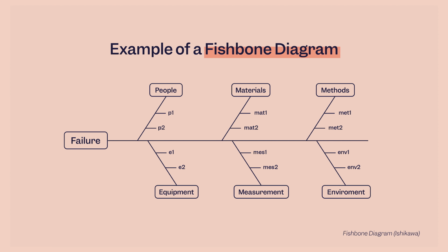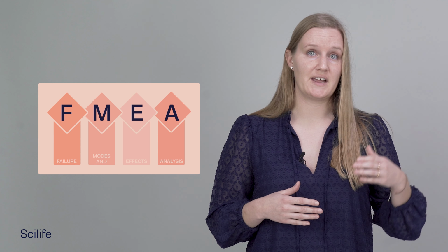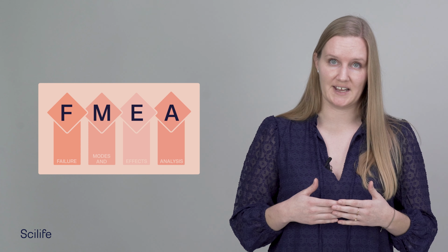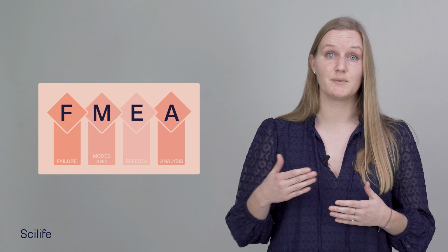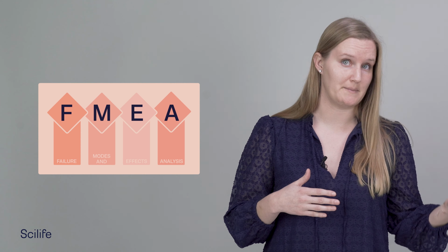The FTA is similar to the fishbone diagram or Ishikawa diagram, although Ishikawa diagrams are designed to identify causes by category. The fault tree analysis and the failure modes and effects analysis not only have similar names, but they are also complementary tools. You can significantly improve your understanding of your medical device hazards and risks if you perform an FTA before you begin the FMEA.